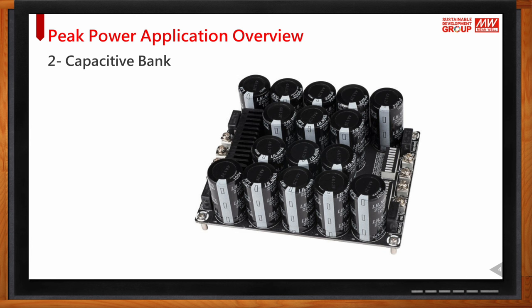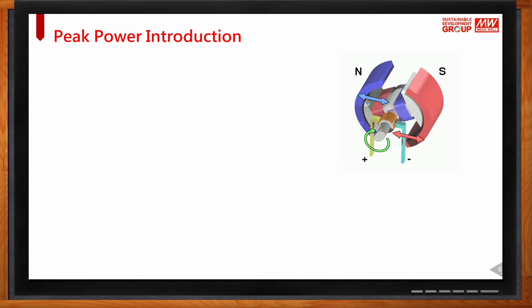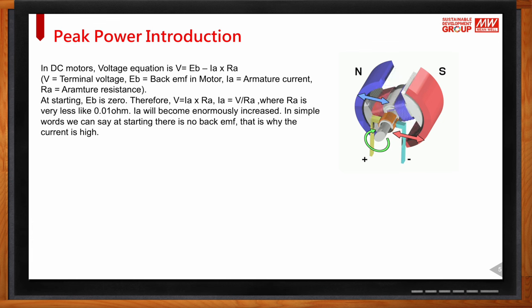So Karim, why do motors and capacitive banks need peak current during startup? When we apply voltage to the terminals, current flows and creates an electromagnetic field, which causes the rotor to rotate — but that is steady state. At startup there is no rotation, and the internal resistance of the winding is very small, so voltage divided by R produces huge currents — five to eight times the rated value. Once the rotor starts rotating, the current drops to the nominal level.